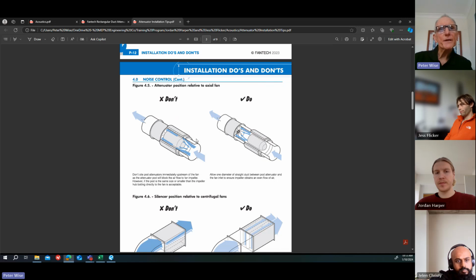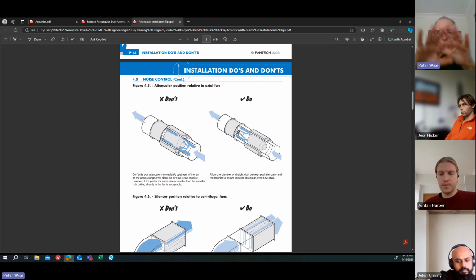Attenuator position relative to axial fan again. Now they've got a podded attenuator this time. This is what I said in the notes. You don't put a podded attenuator at the inlet to a fan because of the turbulence caused by that and the reduced area that the fan blades can see. What the fan blades want to see for an axial fan is nice straight flow to the whole face of the fan. If you put a pod there, you're only allowing the air to go around to the outside tips of the fan, and it just won't function properly. So if you've got a podded attenuator, pull it back and put some straight duct in between the pod and the fan.